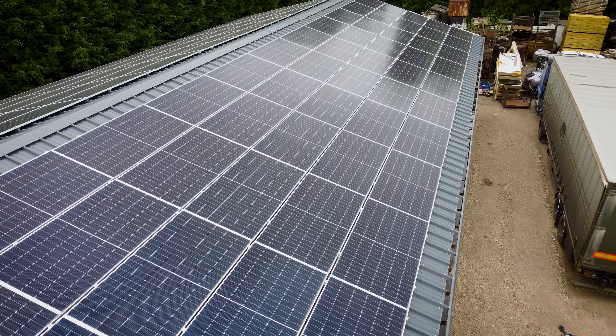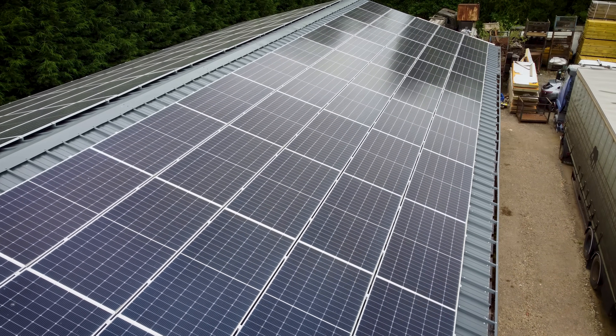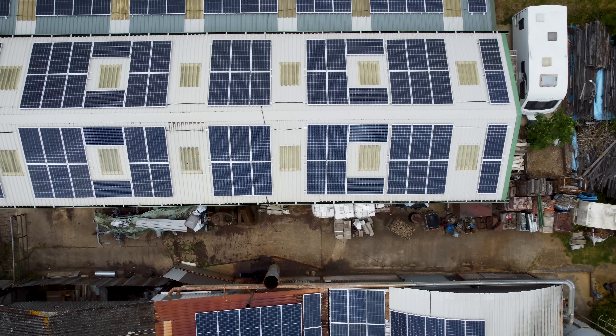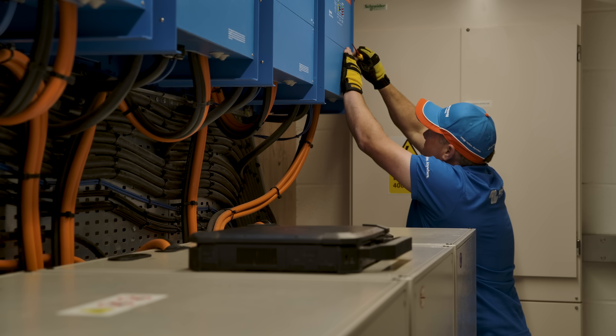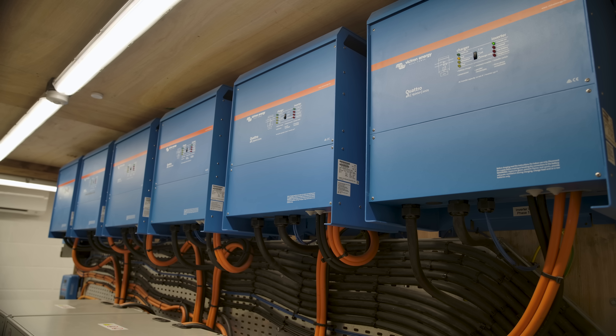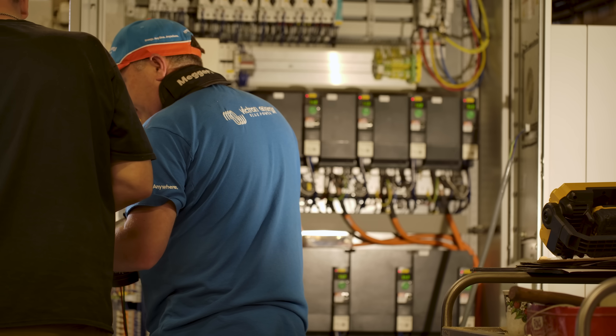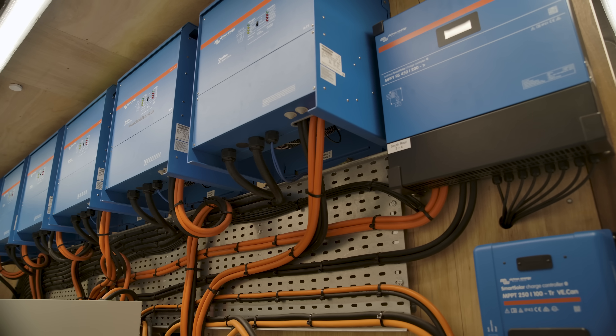Anybody coming along with that was thinking we can't match this. So obviously solar panels wherever we can fit them on the roof — first tick. Then next was how much energy can we get out of the solar panels using the Victron equipment. We did scale it for nine boxes at first — as we call them, blue boxes. But as I got familiar with the factory, doing readings and CT readings, getting the amperages on different days and different times, I started to notice it isn't just ticking over at 60kVA. Sometimes it was going to 75, then 90, and another day it'd be 126. So then we decided to go for the full 12.